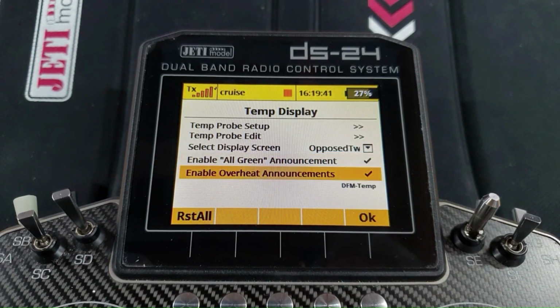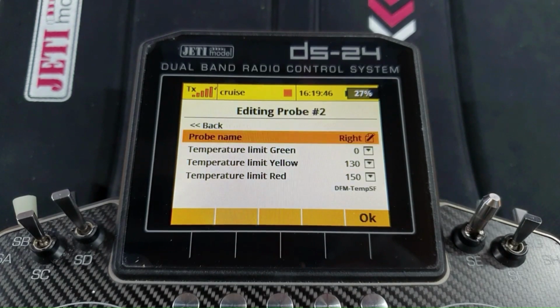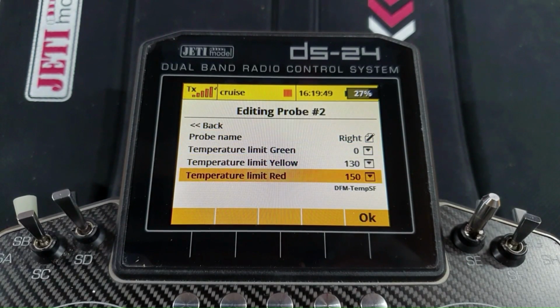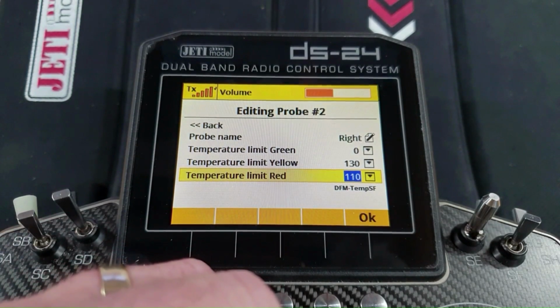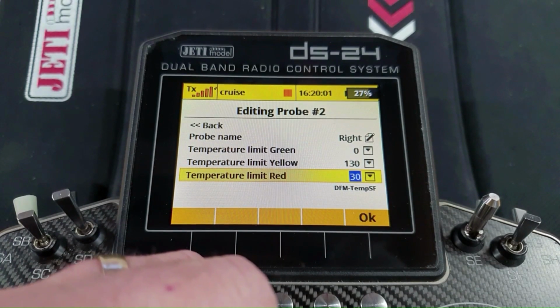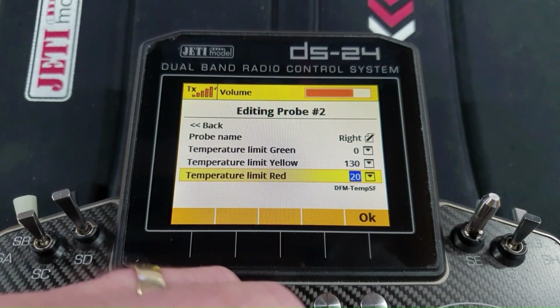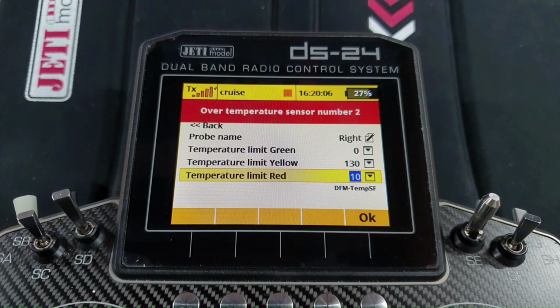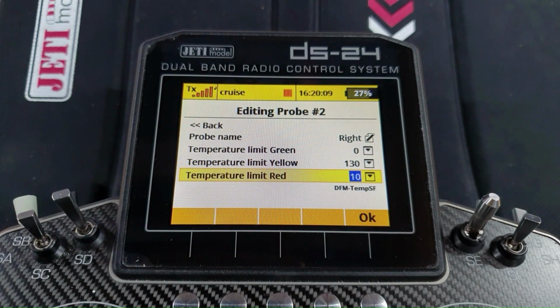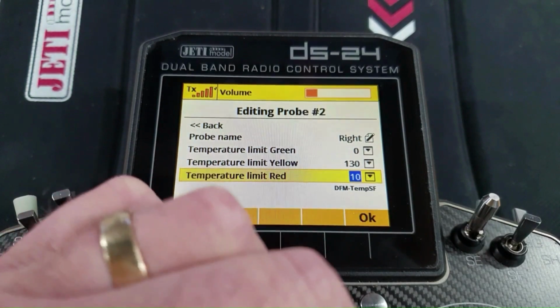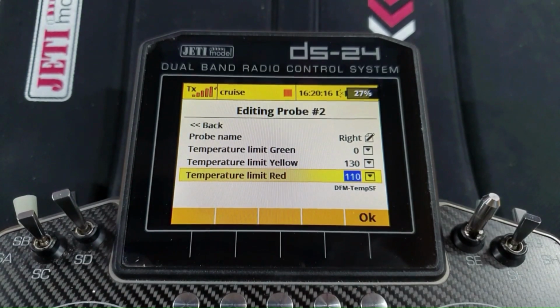So if I go in there - oops, we want temp probe edit - I'll turn the right one down to a nice low value. We'll turn on the volume, and let's get that down to something that's going to trigger the alarm. Over temperature sensor number 2 - there you are, so we know which one has gone over temperature. Turn the volume off, turn that back up again.